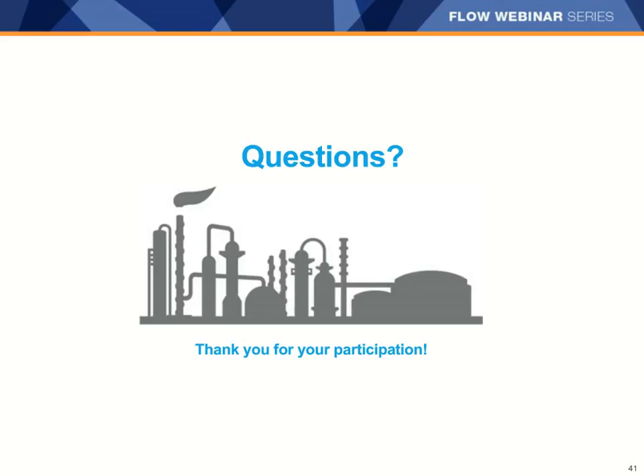This is, again, why we would strongly suggest if you're setting up PVR or net oil for the first time, definitely get your MicroMotion or LBP rep involved so we can help you do that right and explain some of the nuances there to help you get the best density possible. If you are looking at what is my accuracy with the net oil for my oil and water setup, we do have a net oil uncertainty calculator, and we can walk through your particular situation and let you know what sort of accuracy you might expect based on the accuracy that you know your oil and water inputs and on the accuracy of the meter.